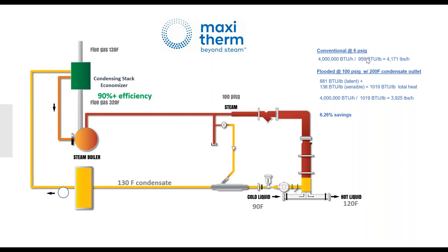Mother Nature says you're taking only latent heat. If you're looking at your steam table, that's 959 BTU per pound. So this is the total pounds per hour you will need at full load. With the flooding design, let's say we operate at 100 psi, condensate leaving at 200 Fahrenheit. Then we extract latent heat and sensible heat out of each pound. Total heat is higher, so we use 6% less steam.